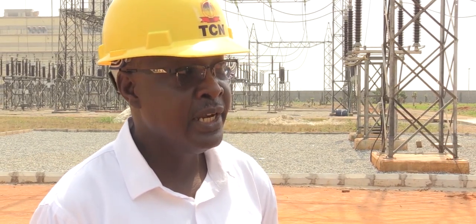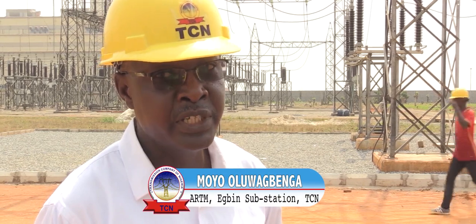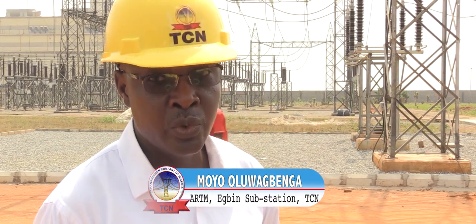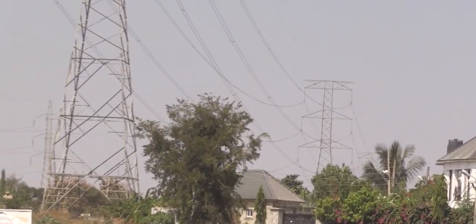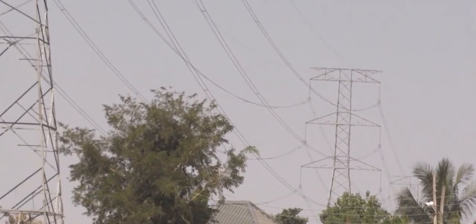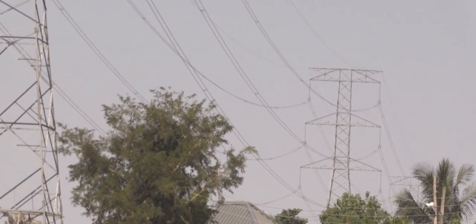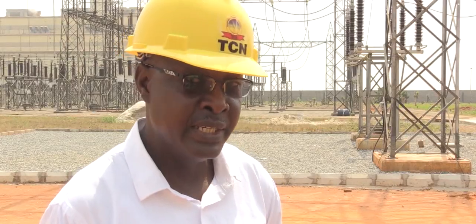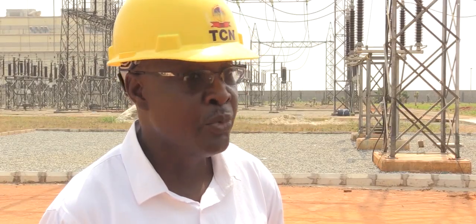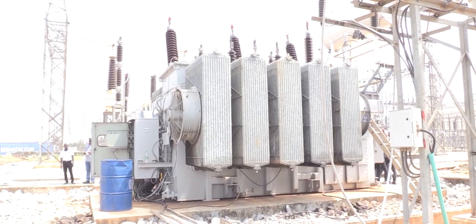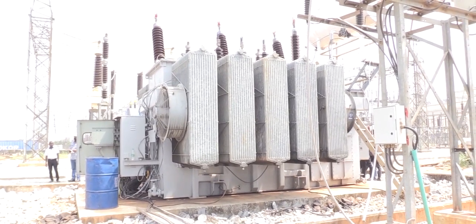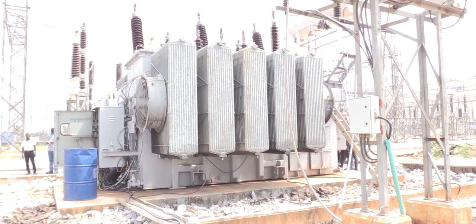We realized that the nearest substation here is about 16 to 17 kilometers away, that is Ikorodu. And the 33 kV feeder radiating is long with so many tie points. So for us to improve the power supply in this environment, that is why the management approved the installation of the 30 MVA transformer, so that we will be close to the consumer. Though we are going to liaise with the DISCO for the radiating of the feeder, the issue of tripping due to long lines will be eliminated by this type of expansion.